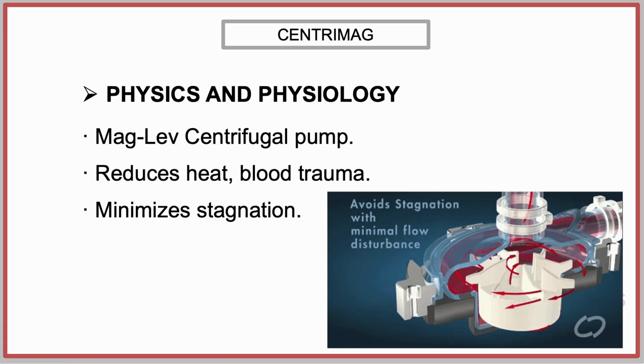This bearingless design eliminates heat production, minimizes blood trauma, and prevents mechanical failure. The rotor surface is uniformly washed by blood flow, reducing stagnation and turbulence within the pump chamber. Mechanical gaps exceeding 0.6 mm minimize shear forces, thereby reducing hemolysis. Blood enters through the inflow cannula, passes through the pump chamber, where the rotating impeller generates centrifugal force, and exits through the outflow cannula at elevated pressure, generating forward flow through the extracorporeal circuit.